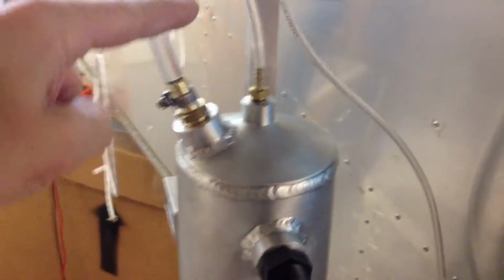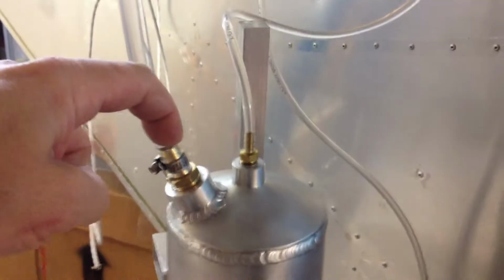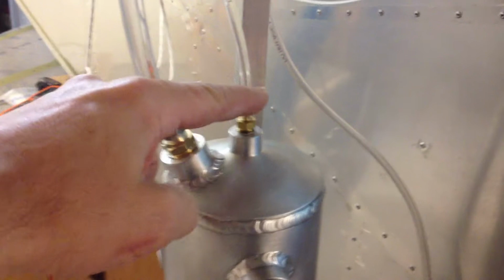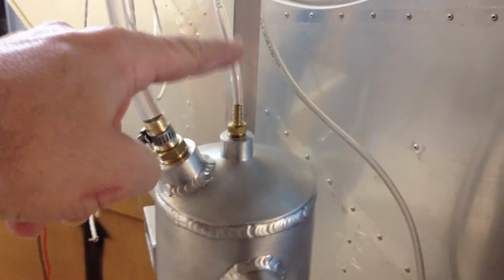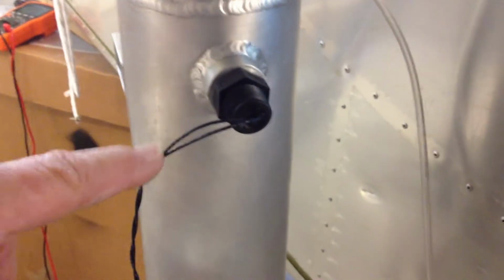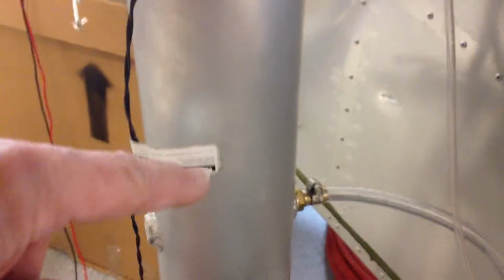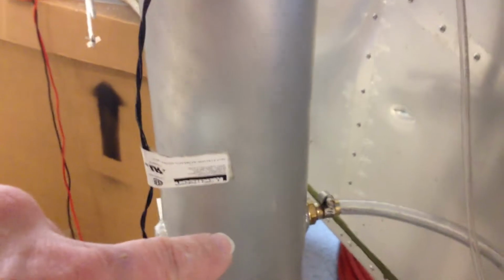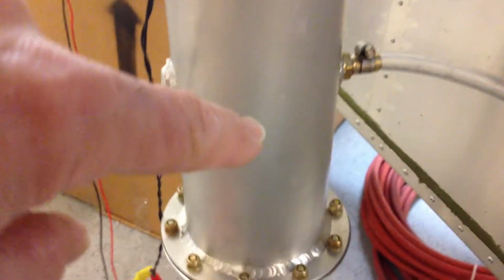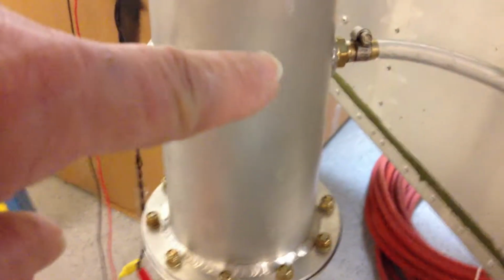First off, this is the fuel line coming down into the header tank, the return line back up, and the vent line that vented all the air back. This is the sensor in the tank that went off when the fuel got to the top of the tank. Normally, the other case would be the alarm going off when the fuel isn't in that position.